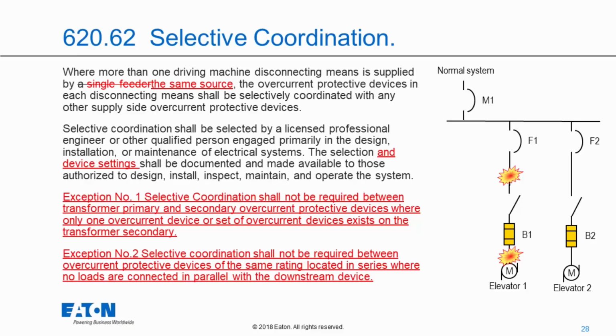The intent is that you do not want to have a fault on one elevator take out the upstream elevator, and there certainly is a possibility that if B1 is not selectively coordinated with M1 and M1 does operate, I can take out elevator 2. They also added some wording about the selection process. Basically, it has to be selected by a licensed professional engineer or qualified person, and the selection and device settings must be documented.